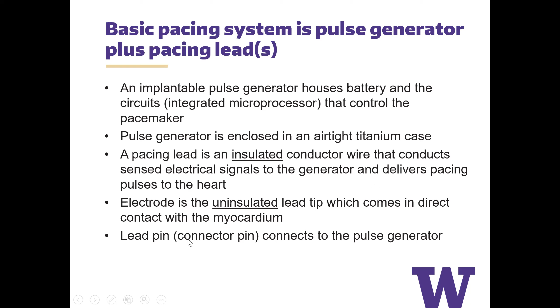The electrode is still part of the lead. It's just the part of the lead that is uninsulated at the very tip and comes in direct contact with the myocardium. And then on the other side of the lead is a lead pin, also called the connector pin, that connects to the pulse generator.